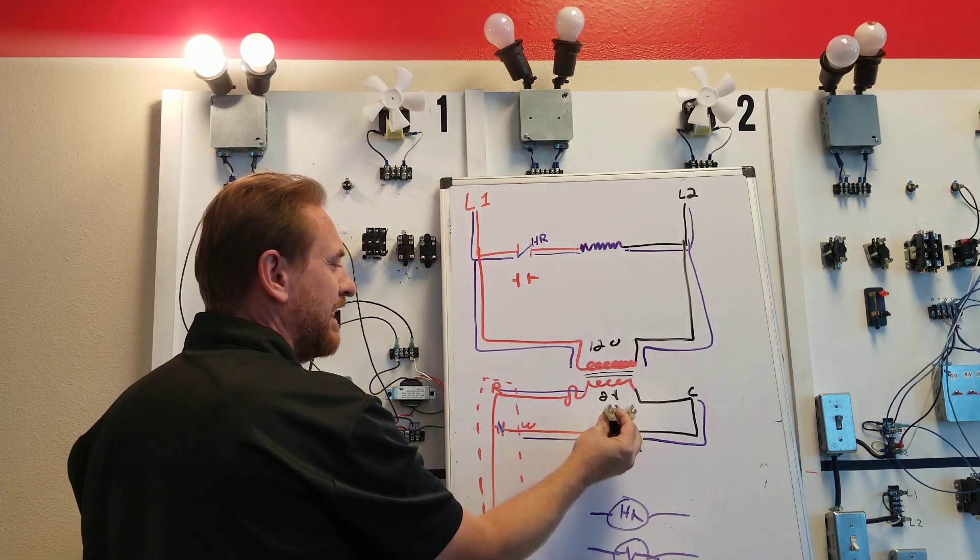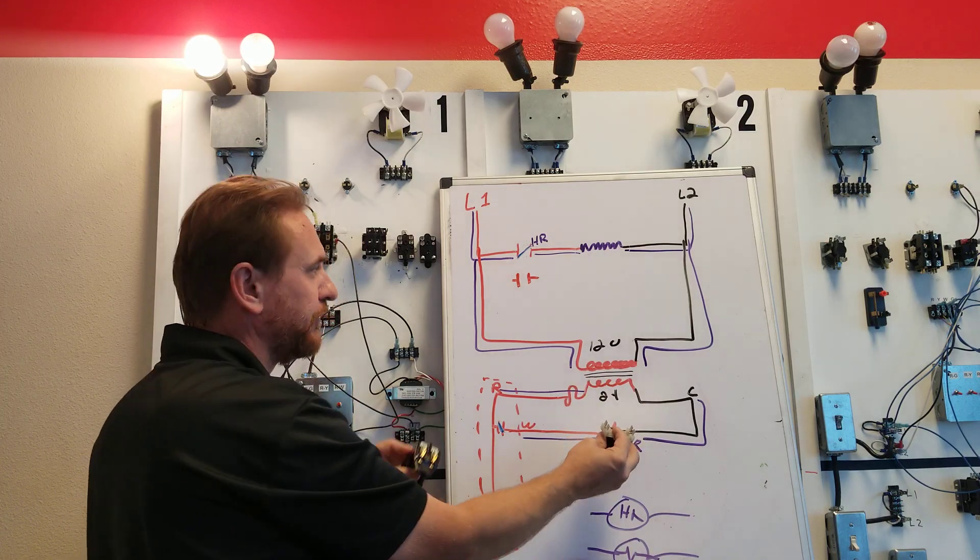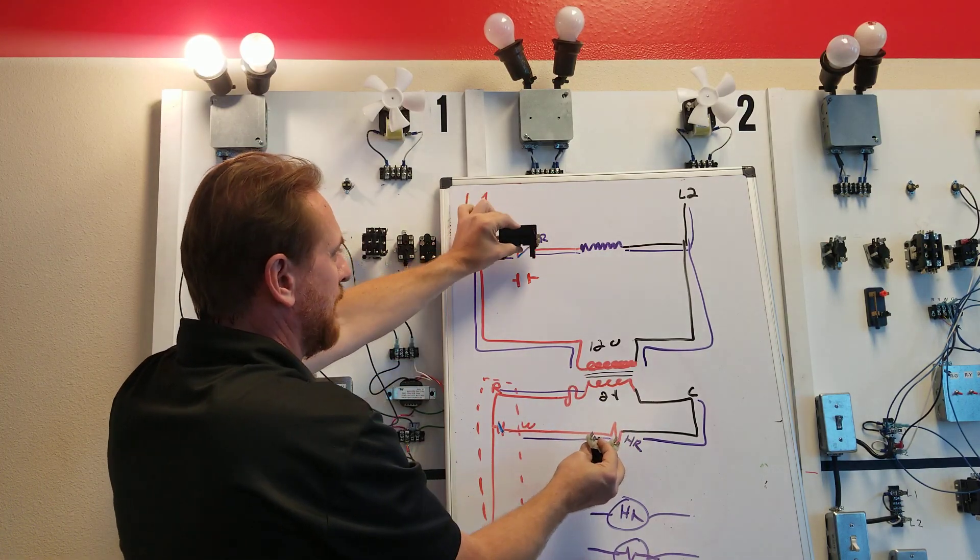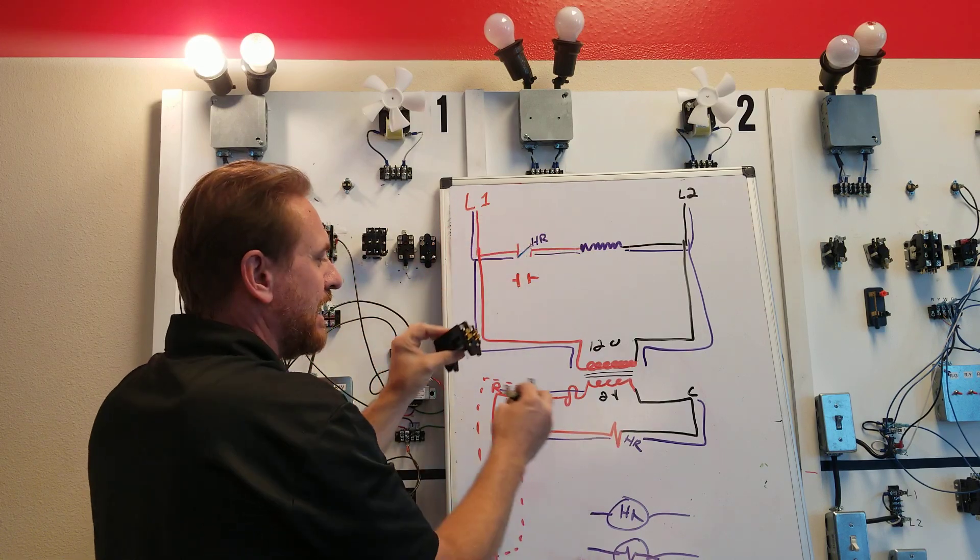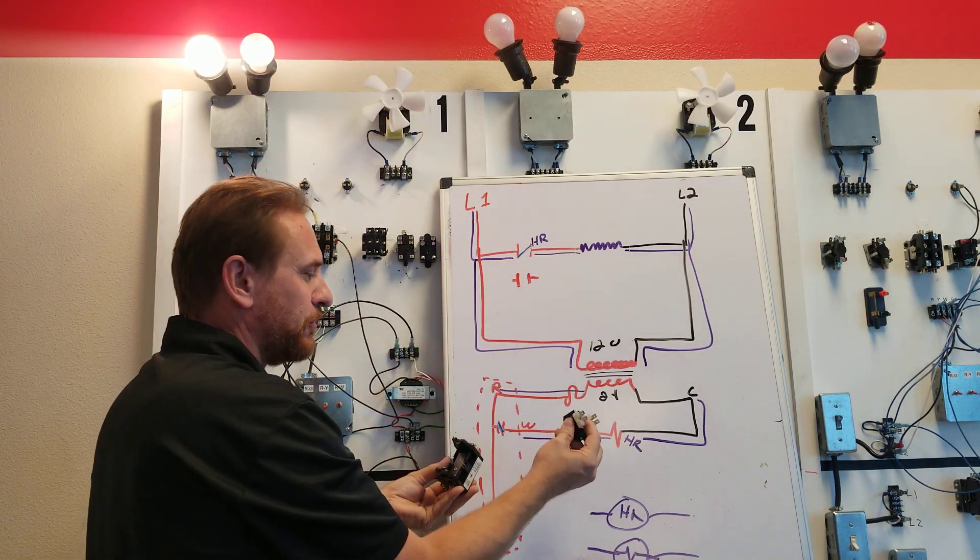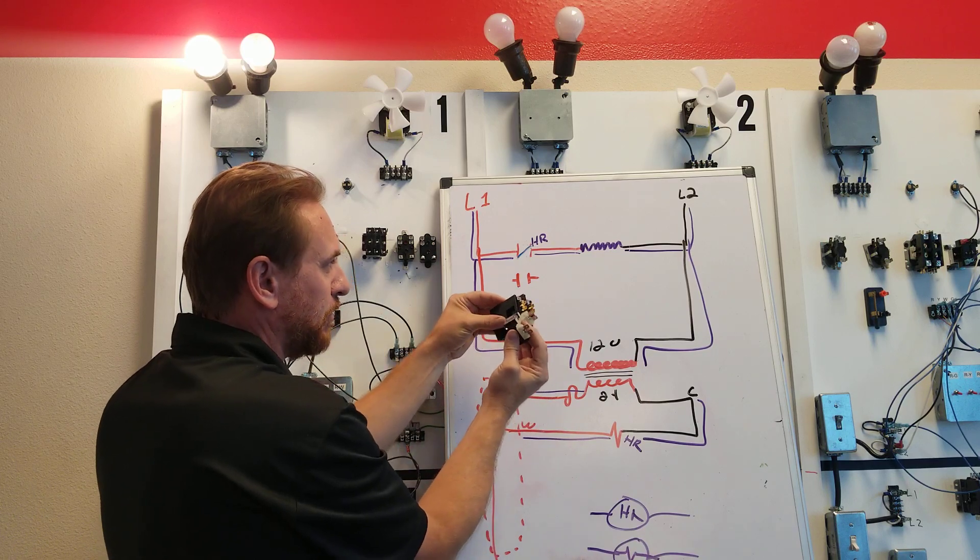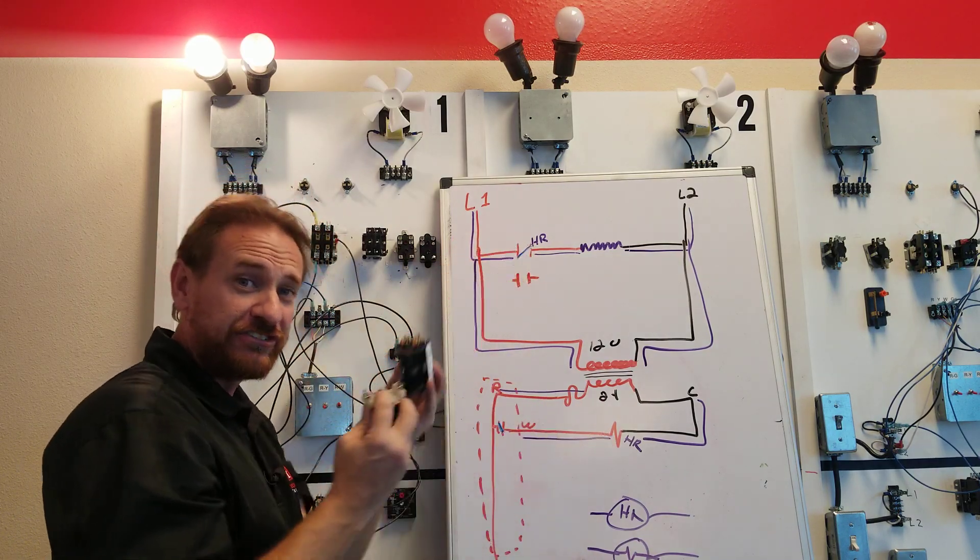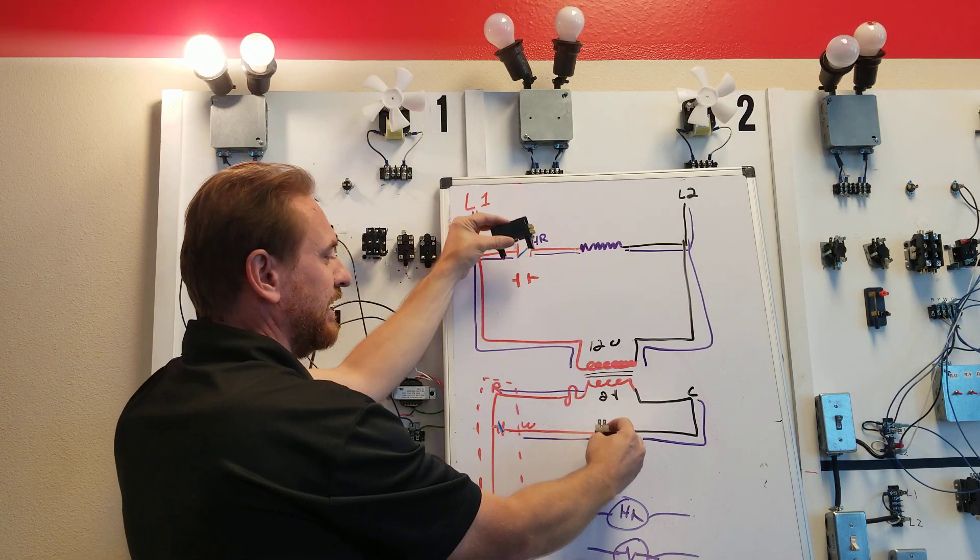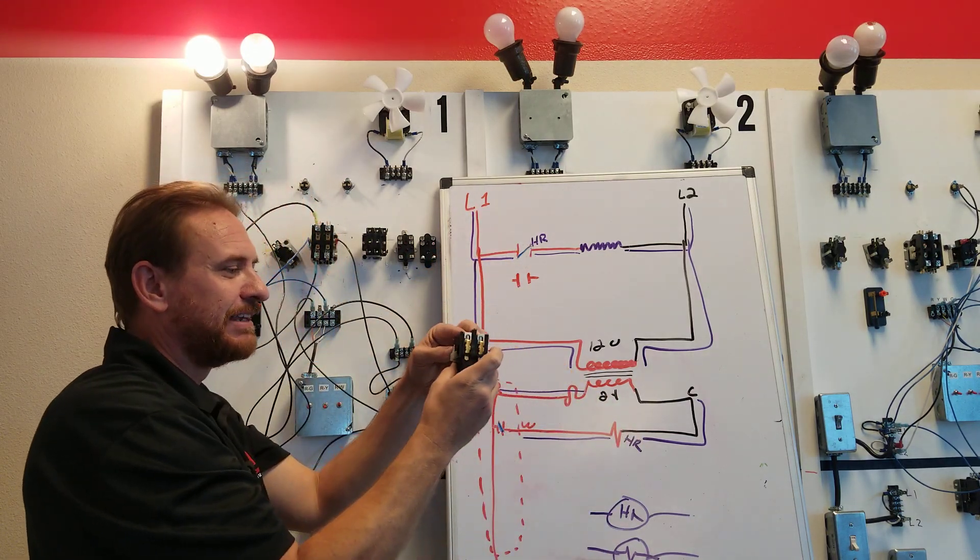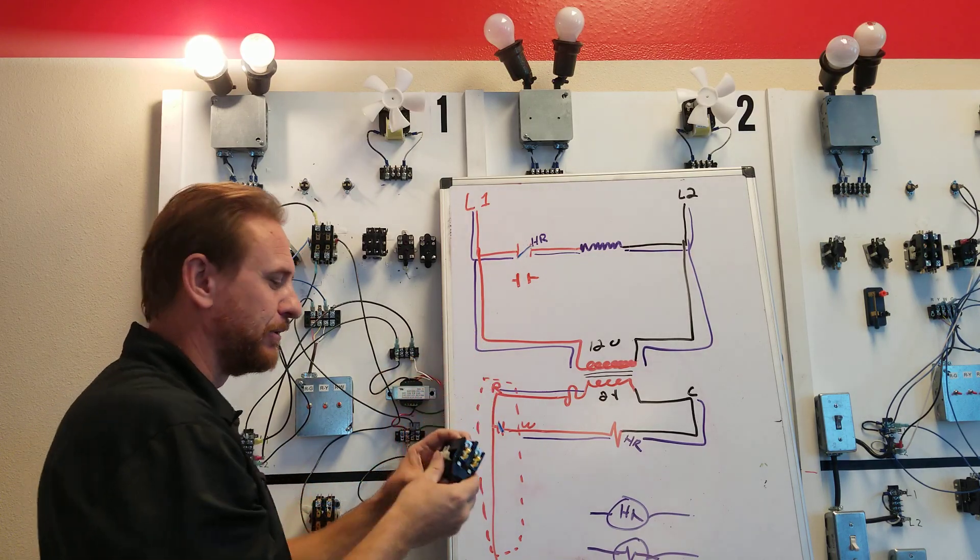Down here is a power consuming device, low voltage 24 volts, and up here is a power passing device sending that power on to a light bulb. Internally they're not touching each other. This electromagnet pulls against the spring pulling these points down. The wires never touch. Same component but they don't touch. They're drawn separately even though it's the same component because wiring wise they are two separate components.